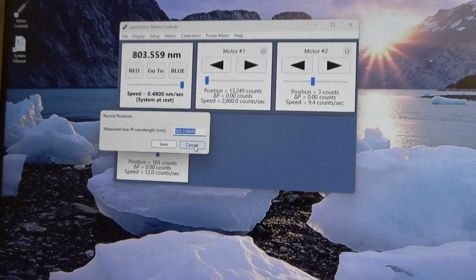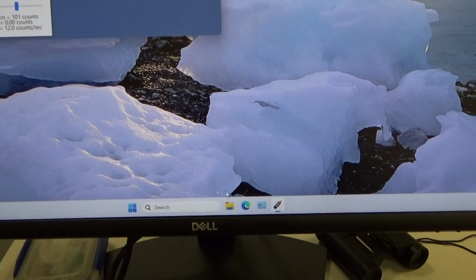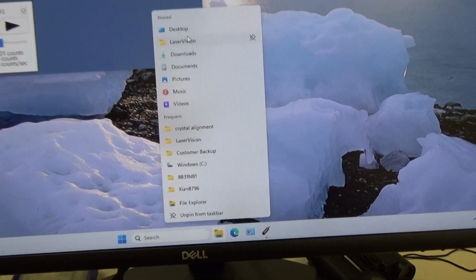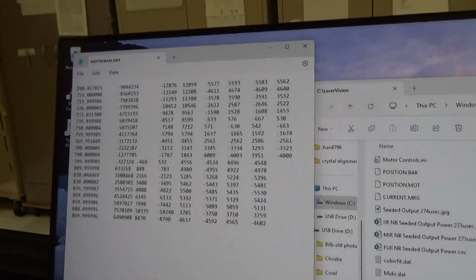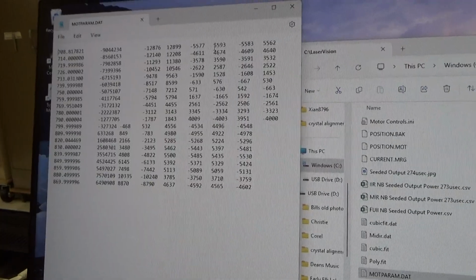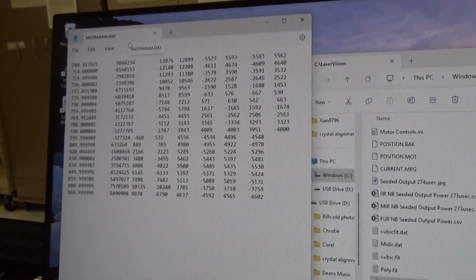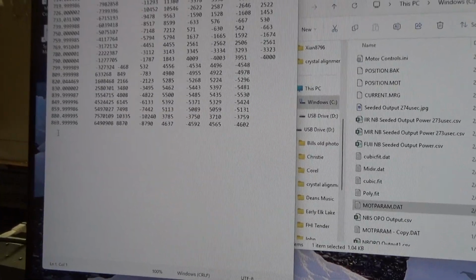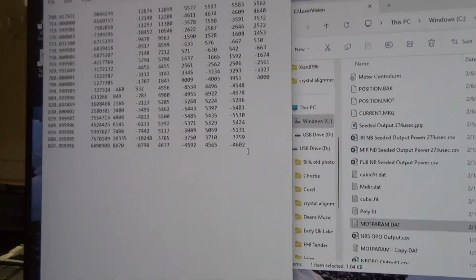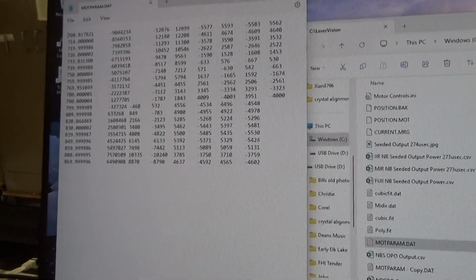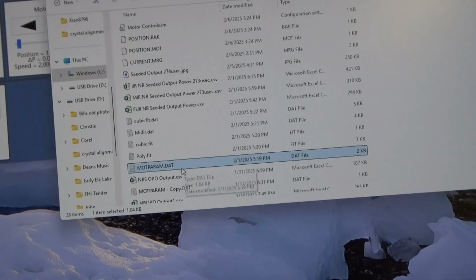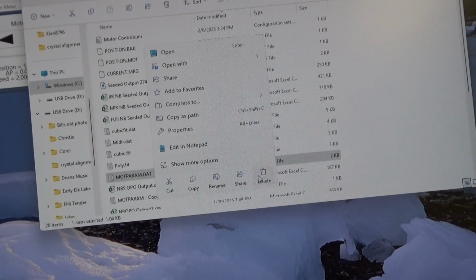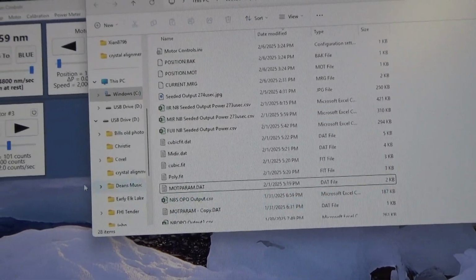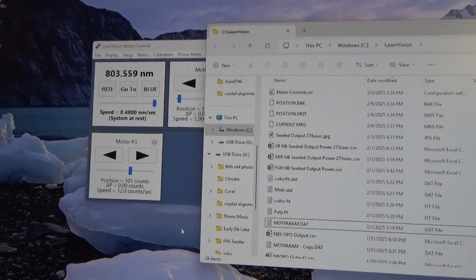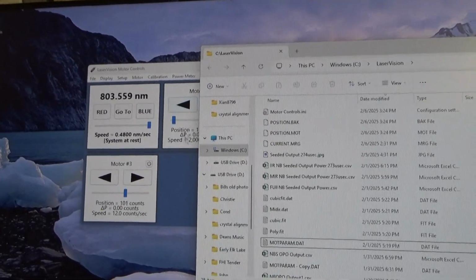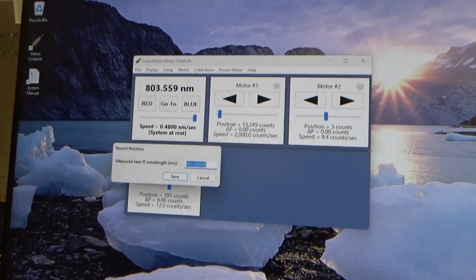When you press save, the program will write those positions out to a file called MOTPARAM.DAT, and this is what it looks like. If the file already exists and there's data in it, the program will just append the wavelength and then the positions of each of the motors in the systems to that file. If you're going to be starting a brand new calibration, it's best to clear all that data out or just delete that particular file, and a new one will be created when you press the F4 and save key to record the motor positions.